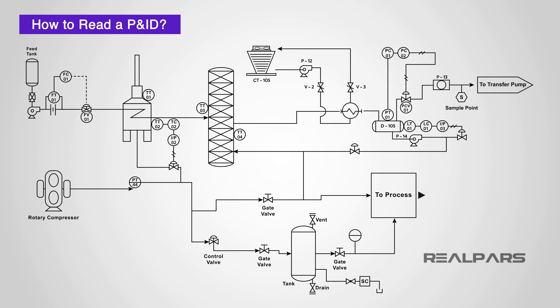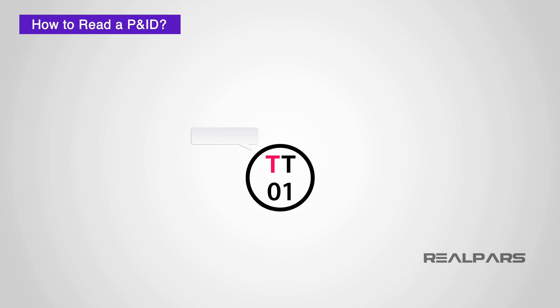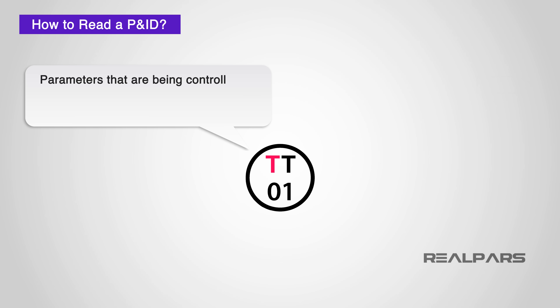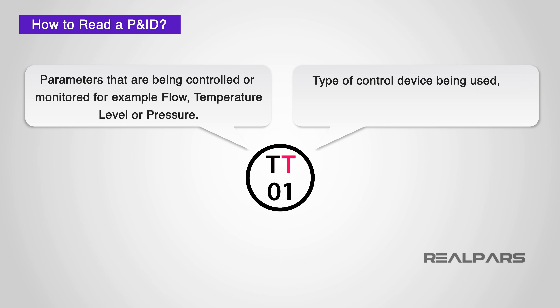The instrumentation codes listed in P&IDs follow a standard format. After some practice reading P&IDs, you will know these codes by heart, but in the meantime there are many resources on the web where you can download these tables for reference. The first letter of the code identifies the parameters being controlled or monitored — for example, flow, temperature, level, or pressure. The next letter defines the type of control device being used, for example, transmitter, valve, or controller.